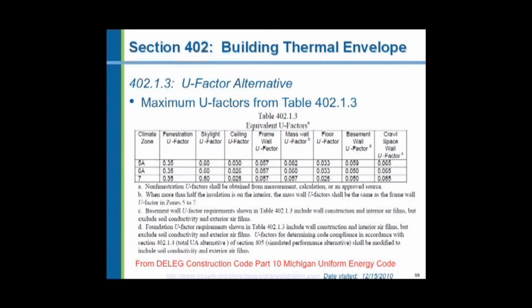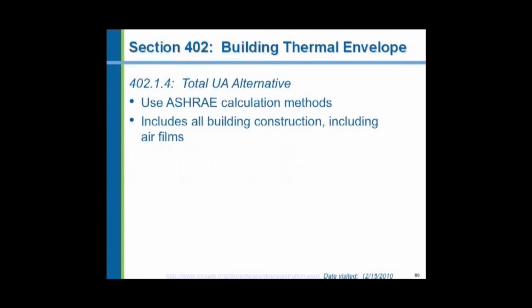Skylight's the same 0.6. Ceiling U value, remember it was an R value of 38, now it's a U value of 0.030. And again, the walls, the mass walls, the floors, the basements, and the crawl spaces are also referenced in U values. You have the option of complying with the prescriptive method of the code and using either method, insulation only or total wall U values. And using the values from this second table, it's called the UA alternative, the U values times the area of the surfaces. And the calculations must be performed in accordance with methods determined by ASHRAE, and that's the American Society of Heating, Refrigerating, Air Conditioning Engineers.